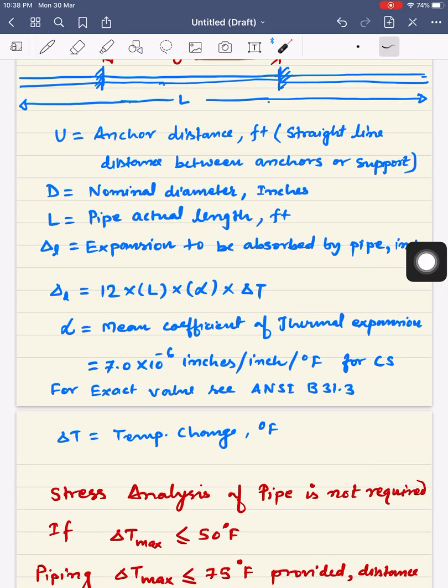Delta L can be calculated by this formula: 12 times L times alpha times delta T, where alpha is the coefficient of thermal expansion, L is actual length of pipe, and delta T is the maximum temperature change.